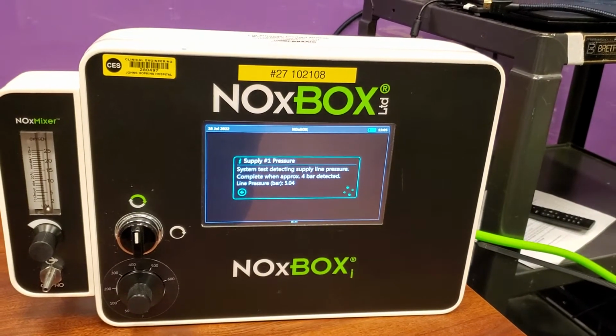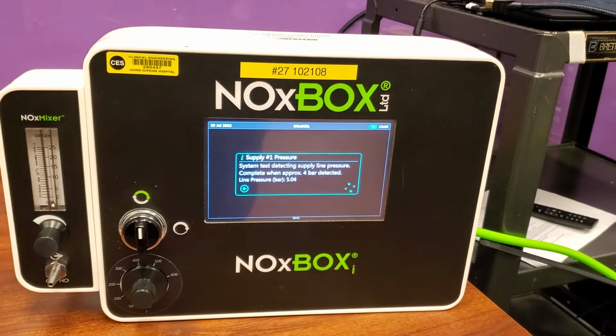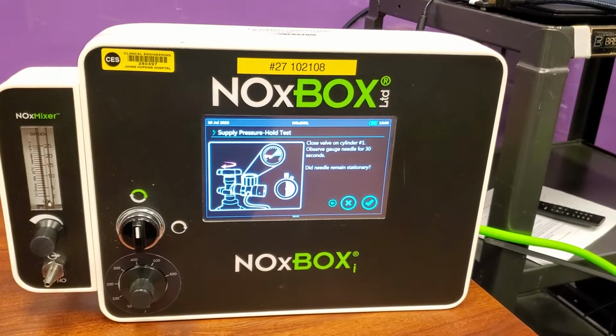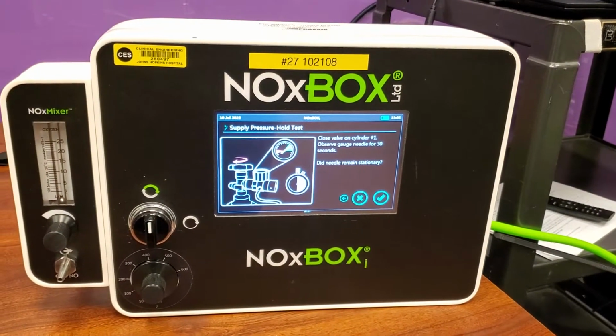Now it's going to detect the pressure. We're going to leave our tank open, and basically it's just checking here to make sure that there are no leaks. So we've moved on to our next test here. Now we're going to close that valve.